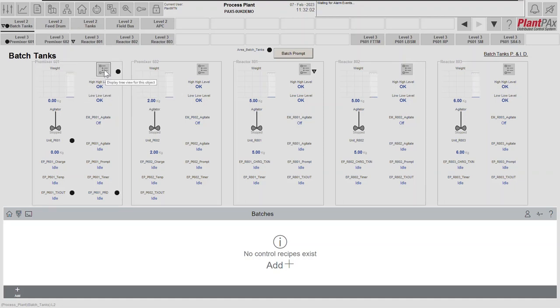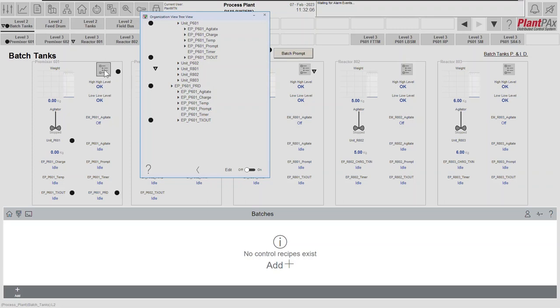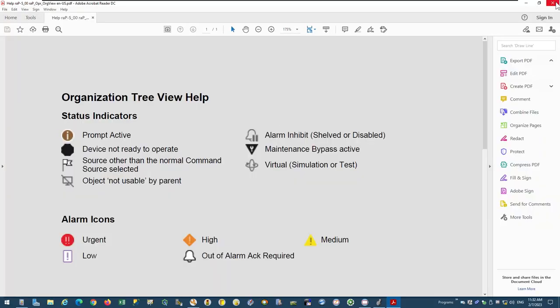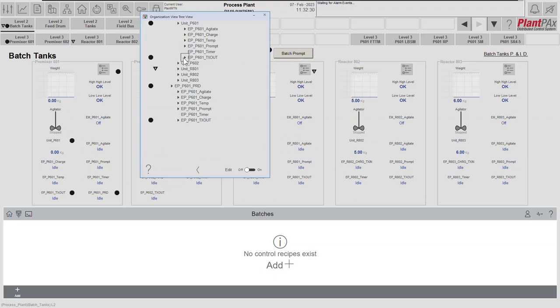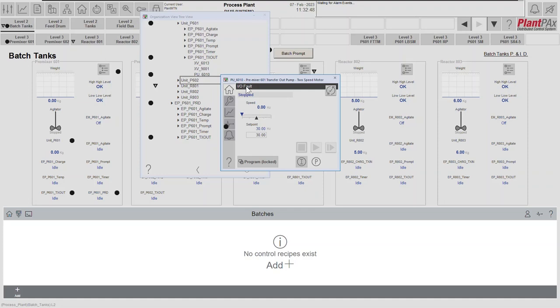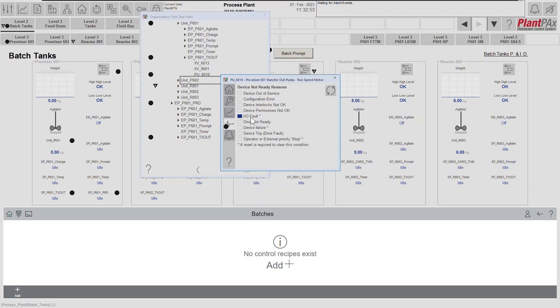From this screen we can open up the organization tree and see what's going on. In the premixer 601 unit, a particular equipment phase has an issue - it has a dot beside it. We can open up the help to see that it means 'device not ready to operate.' If we expand this equipment phase we can see the things it uses as defined by the organization tree, and here we can see that the pump it's using is the device that's not ready to operate. From this device we can directly open up the faceplate to see the details of the problem - the device has an IO fault. Going to the diagnostics tab, we can see the IO fault is present and a reset is required to clear this condition. After performing the reset, the status is propagated all the way back up to the top and everything is now healthy in that unit.